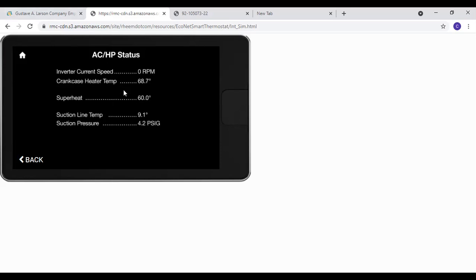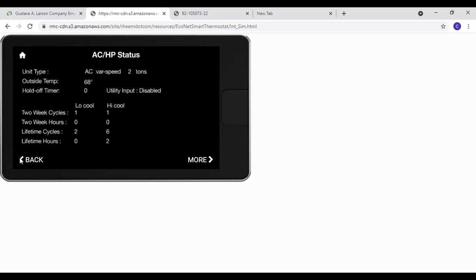Now it'll also tell you what your superheat is, suction line temperature, suction pressure. It will tell you pretty much at a glance everything you need to know. You still don't want to trust it 100%, so you'll want to have gauges on there as you're actually doing the charging.